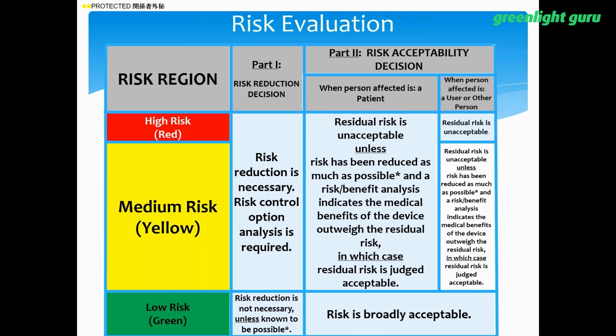If the person affected is a user or other person who is not the patient, then that residual risk is going to be unacceptable, for example, a healthcare provider. Because when you're looking at a patient, we may deem that to get the benefit of that device, that patient may have to undergo an S5 risk. From my perspective, there should never be an occasion where a healthcare provider is undergoing an S5 risk of death using the device. If you have that, then you may have to consider whether or not you have a tenable device.